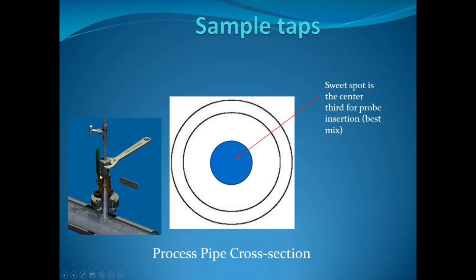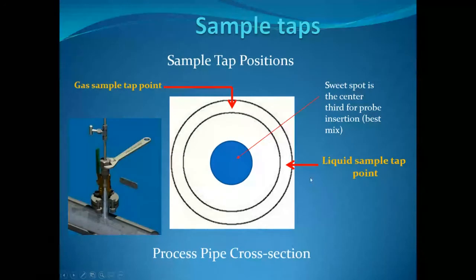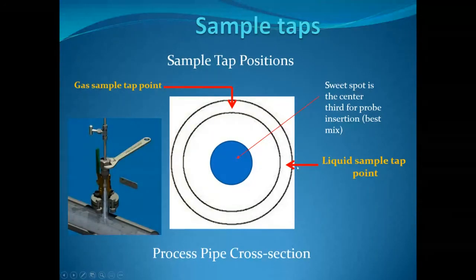One method uses a packing gland with a sample probe that can be raised and lowered, often with indicators showing how deep to penetrate into the sweet spot. The type of sample — gas or liquid — also affects probe placement. Generally, if sampling a gas, you take it off the top, leaving liquids at the bottom. If sampling a liquid, take it off the side of the pipe, leaving gases at the top and solids at the bottom.